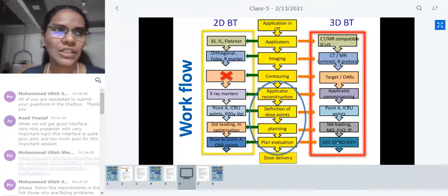So first step in the treatment planning process as a physicist, I would consider is the applicator reconstruction. When the imaging is done, the first process that you do is the applicator reconstruction. There are 2 ways of doing it. One is manual, or it's also called direct reconstruction. And second is applicator library-based reconstruction. If you are a BEBIG user, then it is by default. For Elekta and Varian users, it can be optional, or it can be a license that needs to be purchased. So what do you mean by direct or manual reconstruction?